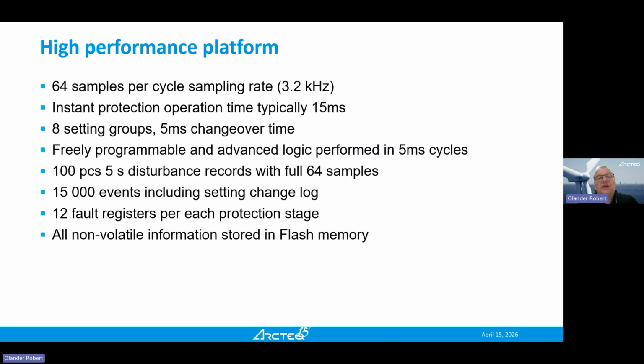Then if we look at the platform on the device, of course we are talking about analog signals, which we convert to digital signals. So it depends on the sample rate how well you will represent the analog signals. And we have actually quite a high sampling rate compared to other products on the market, 3.2 kilohertz. So we will get 64 samples per cycle. Fast protection, instant protection, depending of course on what type of protection it is, but the fastest possible, like overcurrent protection, can be in 15 milliseconds. We have 8 setting groups for each protection stage with a 5 millisecond changeover time.